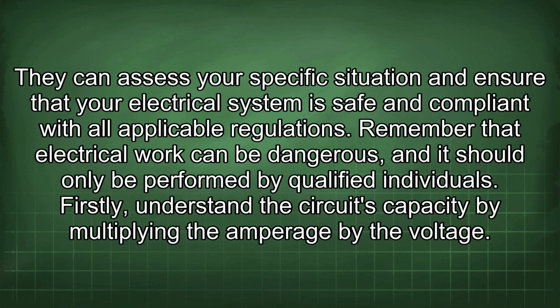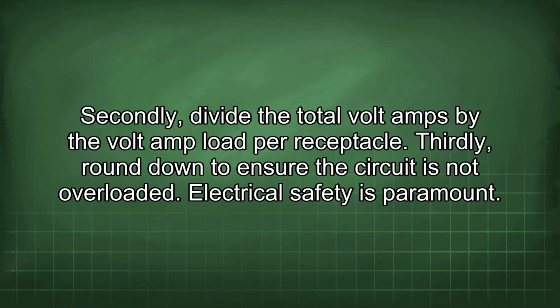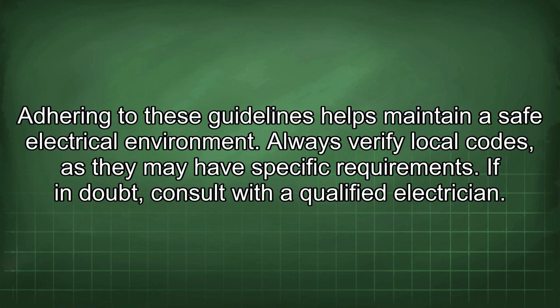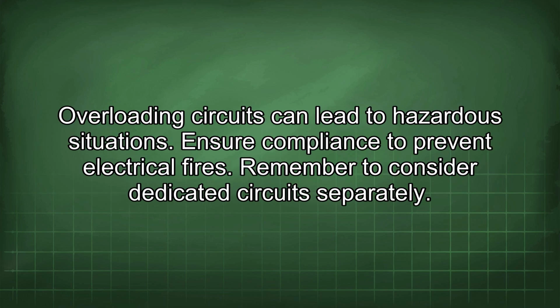Firstly, understand the circuit's capacity by multiplying the amperage by the voltage. Secondly, divide the total volt amps by the volt amp load per receptacle. Thirdly, round down to ensure the circuit is not overloaded. Electrical safety is paramount. Adhering to these guidelines helps maintain a safe electrical environment. Always verify local codes, as they may have specific requirements. If in doubt, consult with a qualified electrician. Overloading circuits can lead to hazardous situations. Ensure compliance to prevent electrical fires.